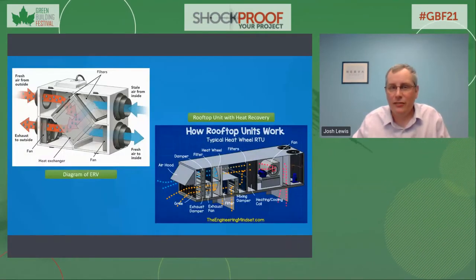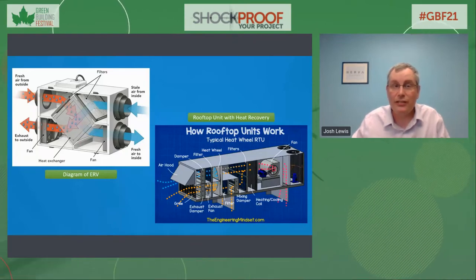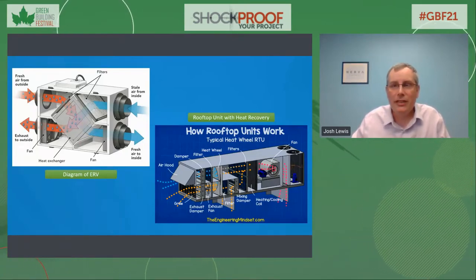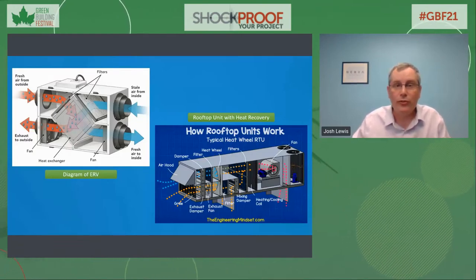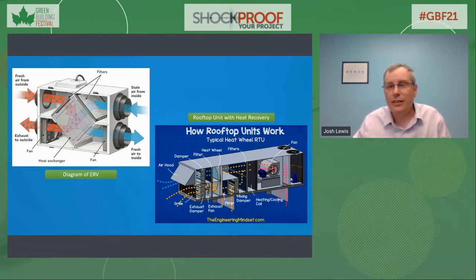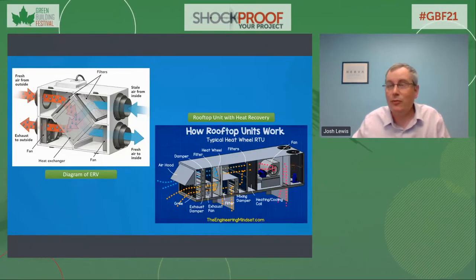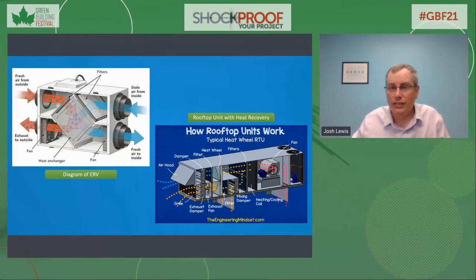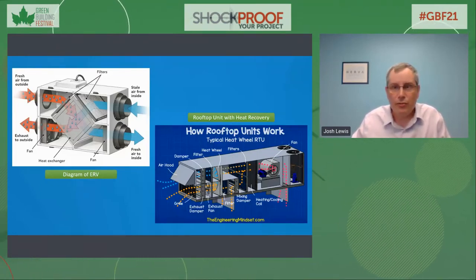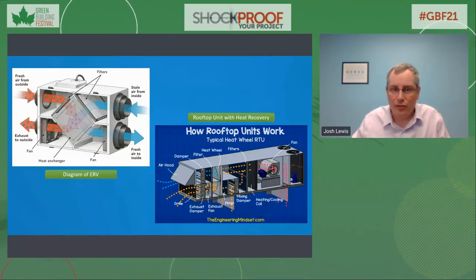Now, the inherent loss of energy efficiency when bringing fresh air into a building can be mitigated if the HVAC systems in the buildings recover heat, or both heating and cooling, from the inside air being exhausted to make room for the incoming fresh air. This is typically accomplished with systems that perform heat recovery ventilation, also known as an HRV, or energy recovery ventilation, also known as an ERV.